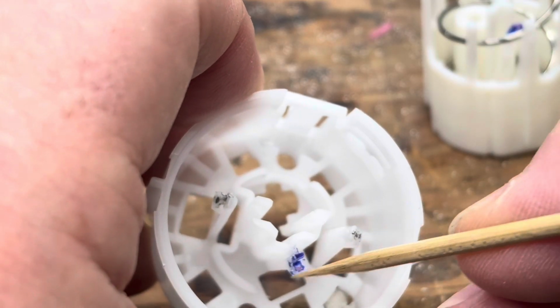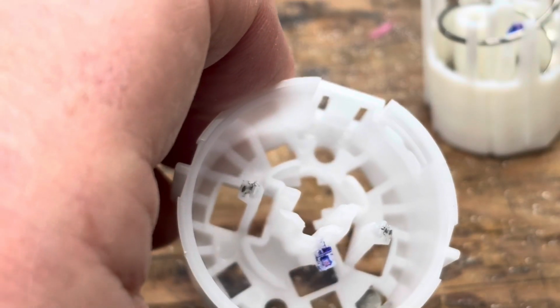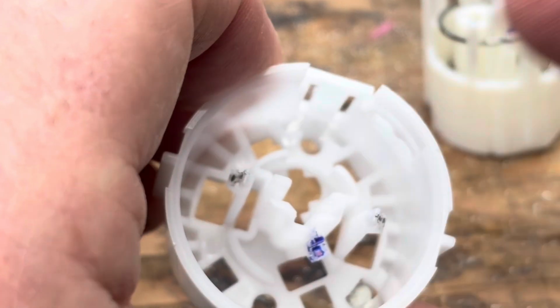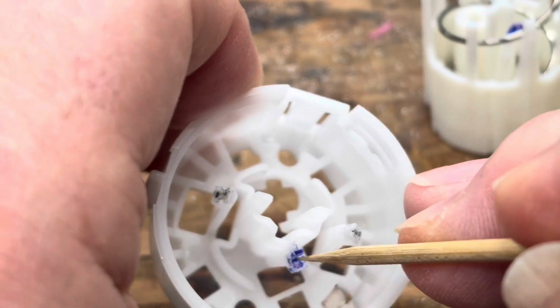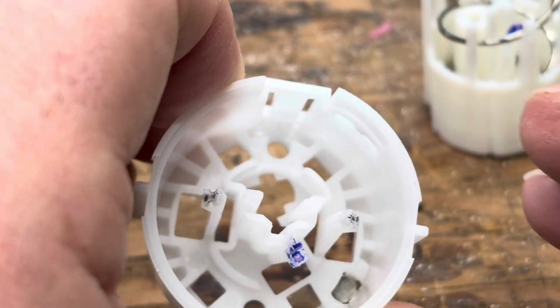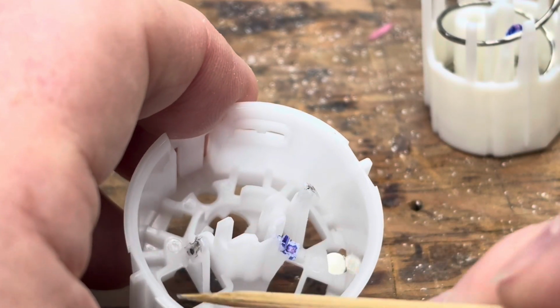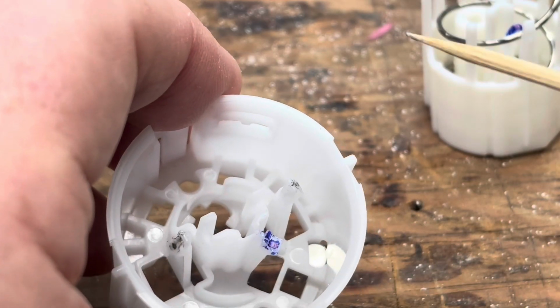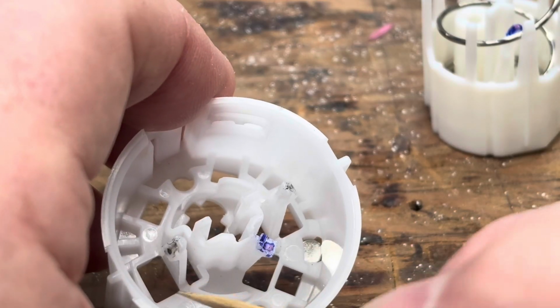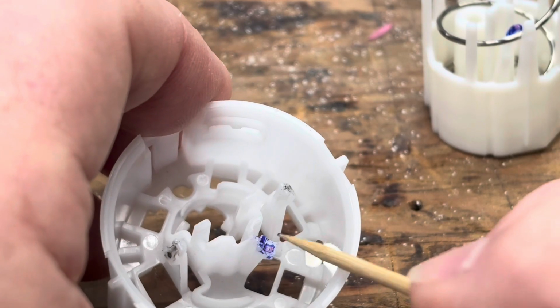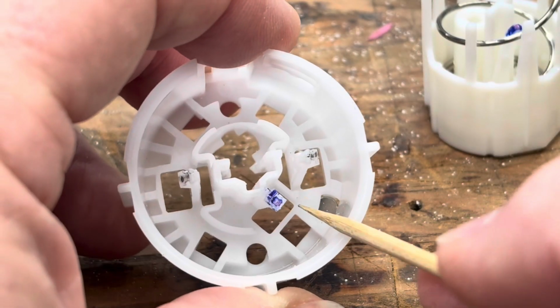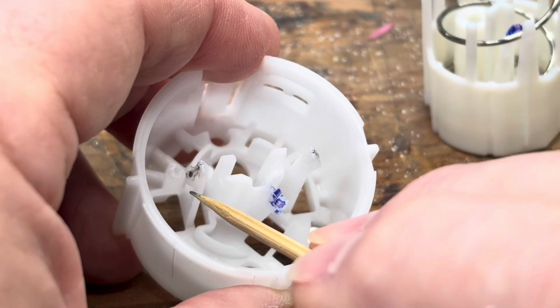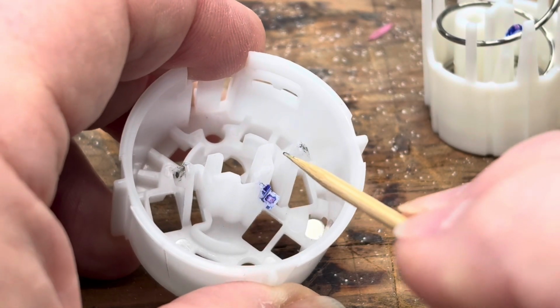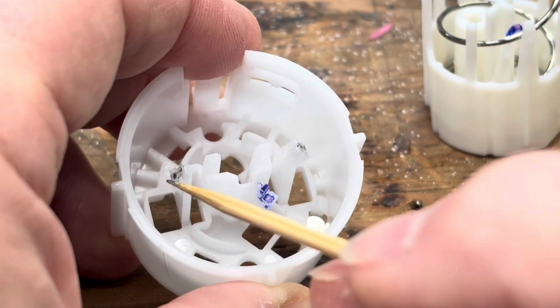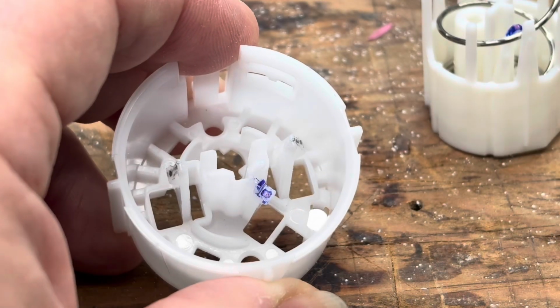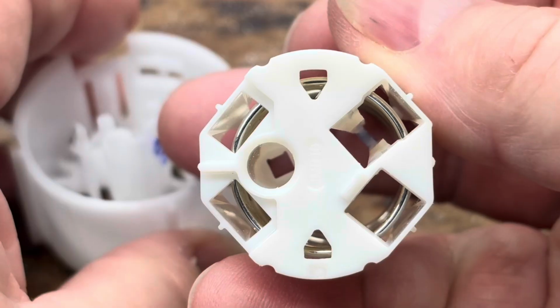Once fired, this blue platform is what prevents 4 from sliding back into 3 and exposing the needle. So once it locks back here, 4 locks back here, so the needle can't get back out. These 2 black tabs fit inside what I call the pinch receptacles. There's a spring that fits around the outside of these 2 prongs, fingers I'll call them, and hooks under these shoulders, and that exerts inward pressure, a pinch motion, and then these 2 pinch points fit in those corners.